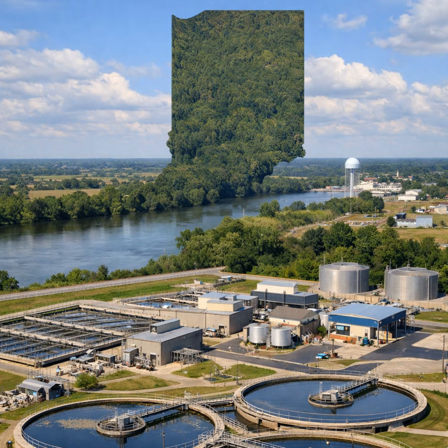Step feed aeration. Step feed aeration is a modification of the conventional activated sludge process. In step feed aeration, primary effluent enters the aeration tank at several points along the length of the tank, rather than at the beginning of the head of the tank, flowing through the entire tank in a plug flow mode.